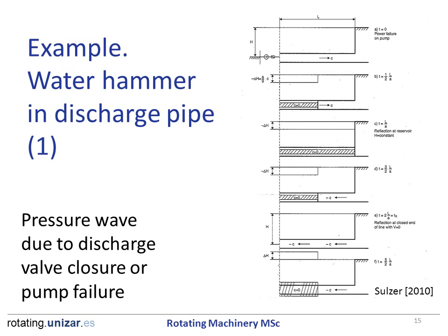This is an example of the pressure wave induced by a sudden closure of the discharge valve or a pump failure. At A, you can see the initial condition — the pump is pumping a liquid to the reservoir. After the valve is closed, the fluid stops and a depression is formed which travels downstream (diagram B). The wave reaches the reservoir (C) and reflects back to the pipe, inducing a negative velocity and restoring the pressure (D). When this wave arrives again to the valve (E), the fluid is stopped and a new pressure wave is propagated downstream (F).